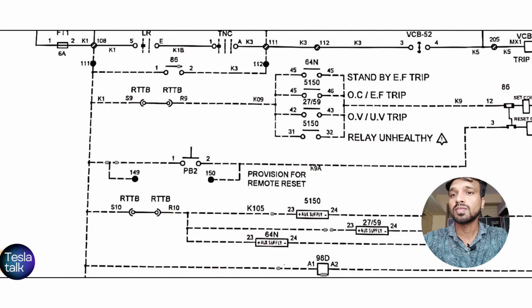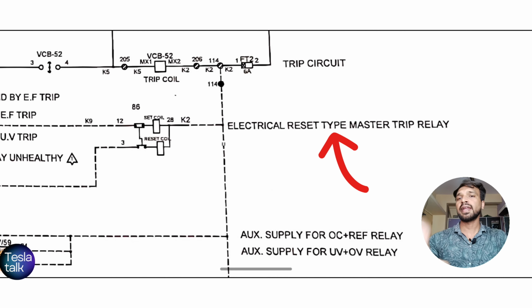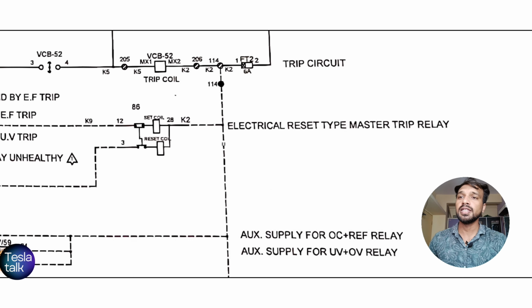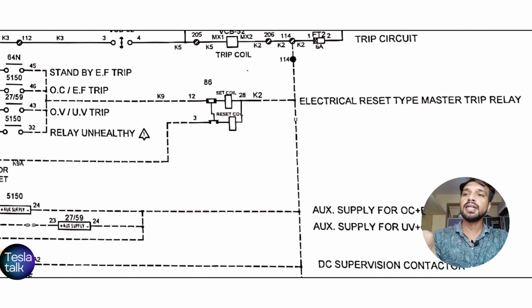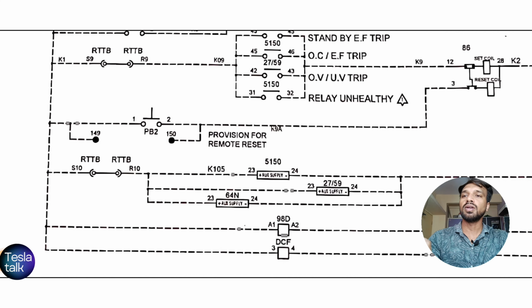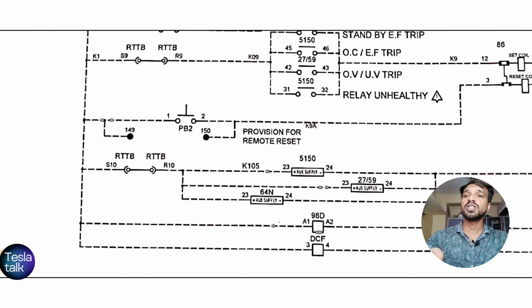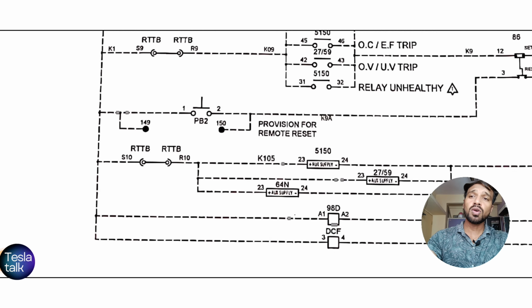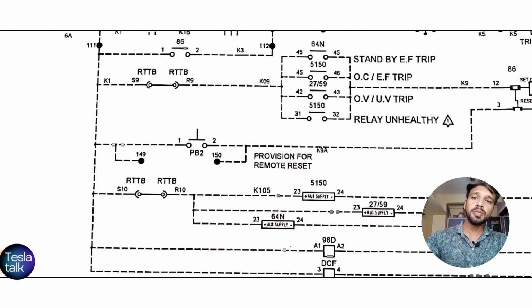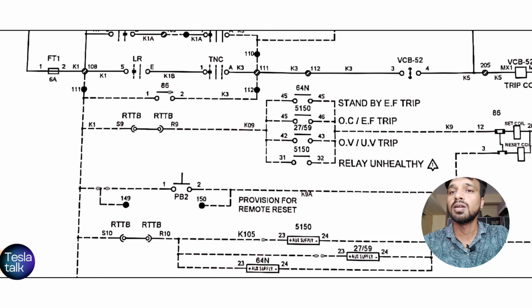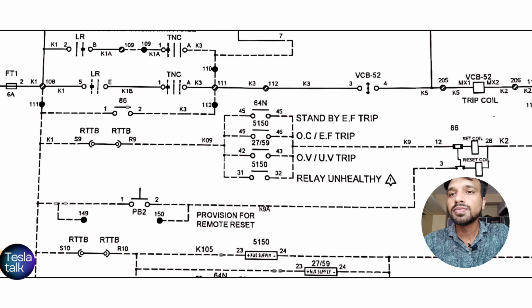So this is the electrical reset type master relay. Electrically reset means we can reset the master trip relay electrically. And how will it reset? It will reset by this contact. There is a push button given here, a provision for remote reset. You can remotely reset the master trip relay or just push this push button. This one is also used for local tripping.